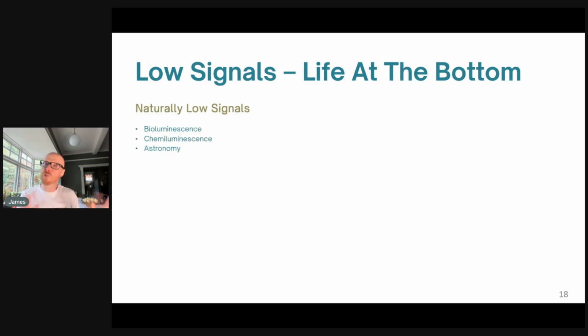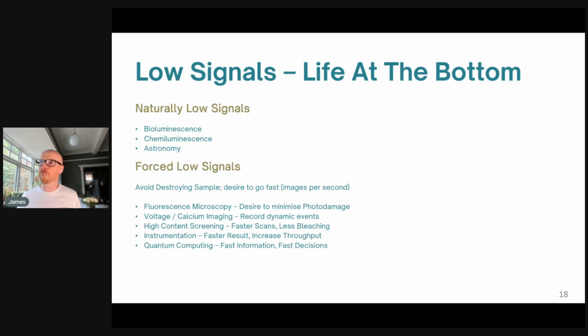Now, there are naturally low signals. There's bioluminescence and chemiluminescence and astronomy. These are naturally low photon emitting signals, right? Now, it's not the fault of the star in a distant galaxy. It's trying its hardest. It just turns out that the photons arrive here in pretty low numbers relative to our exposure times. But these are naturally low. Most of the time, we create the problem of low light. We have forced low light on ourselves.